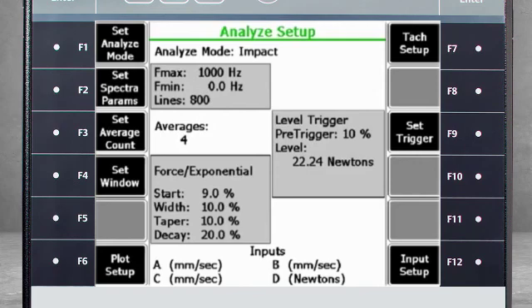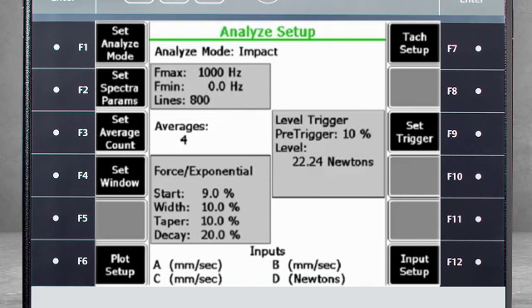The trigger level defaults to 22 newtons. Typically, if the data acquisition starts prior to impacting the structure, the analyzer may incorrectly interpret any background vibration more than 22 newtons as the impact hammer pulse. This would require you to increase this level. The opposite can also be true. If the structure is very rigid and you impact it with a hammer, you may not be able to create sufficient energy to recognize the pulse. In this case, you would need to reduce the level of newtons.